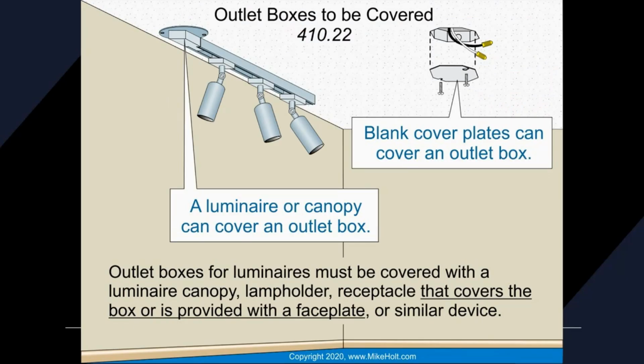All right. Outlet boxes are to be covered. So this is not so much a thing anymore, but I've installed a ton of track light and taken down a ton of track light. Outlet boxes for luminaires must be covered with a luminaire canopy, lamp holder, or receptacle that covers the box, or is provided with a faceplate or similar device. So you can see this track light has to cover the wiring. Can't have exposed wiring when you're doing a track light.